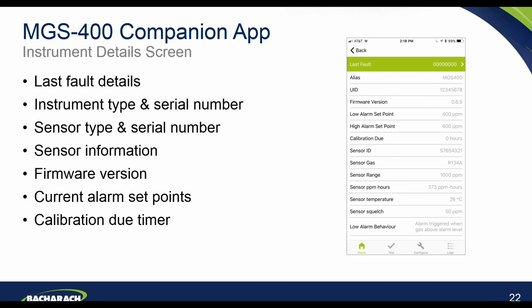The instrument details screen, as you can see here on the right, is really used to give an overview of the setup of the instrument as it is at the time of connection. It will show you the last fault details, the instrument and sensor type and serial numbers. It will show you sensor information, the firmware, and also your alarm set points. It will also show you here the calibration due timer, so it will show you the countdown to the next calibration due. On this particular screen, it's really a reference screen. There is no option here to change any of these configurable items from this particular screen.